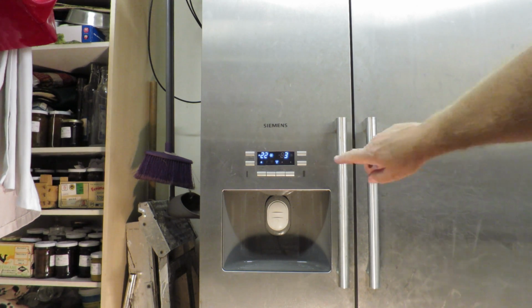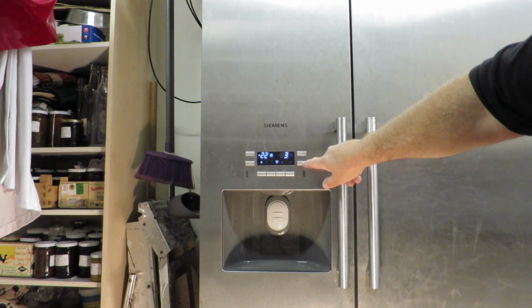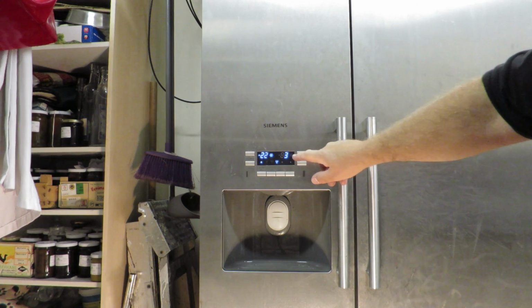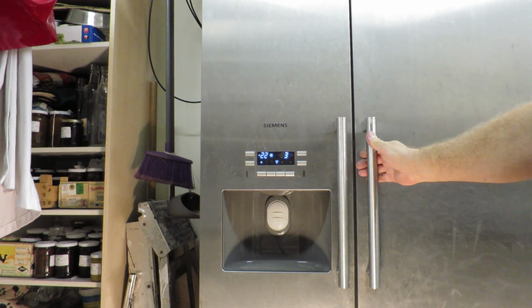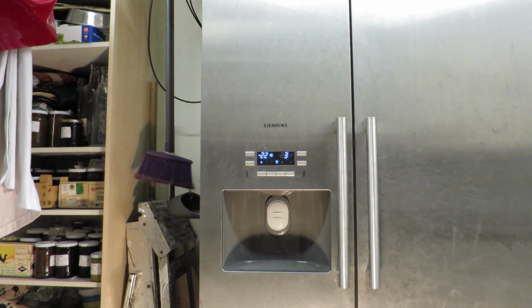You can do the same test for super on this side. Press on super, wait till your fan side comes on, open the door, then press the little automatic switch which turns the light off, and listen for the fan coming on. That's a simple test to make sure the fan is working on both sides.